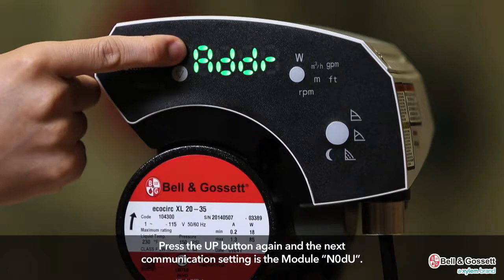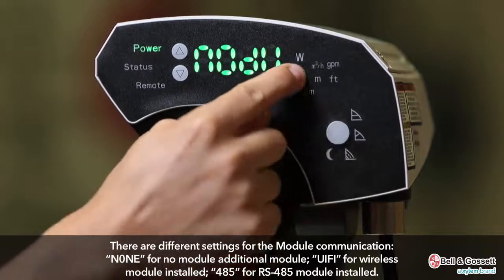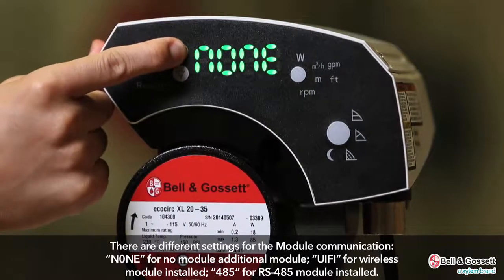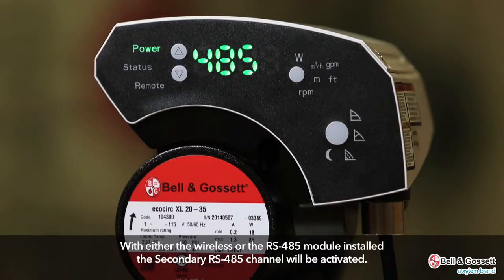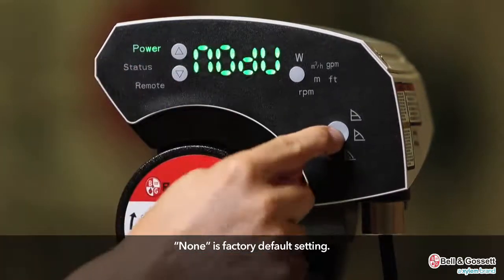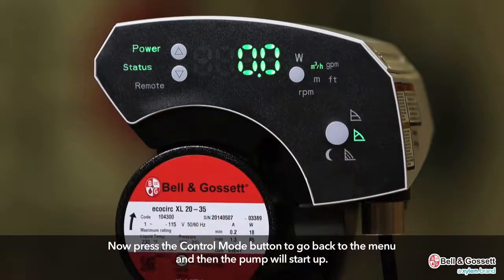Press the parameter button to select the value, then press the control mode button to go back to the communication menu. Press the up button again and the next communication setting is the module, NODU. The available settings are: NONE for no module, UIFI for wireless module installed, and 485 for RS-485 module installed. With either the wireless or RS-485 module installed, the secondary RS-485 channel will be activated. None is the factory default setting. Press the control mode button to go back to the menu and the pump will start up.